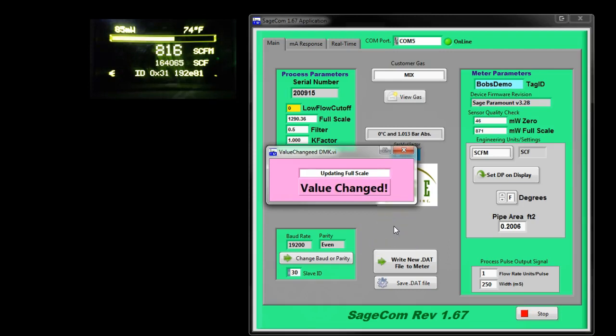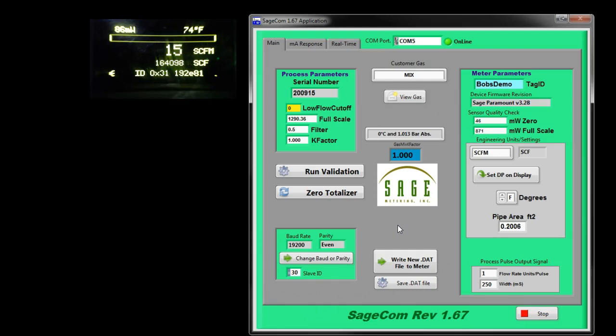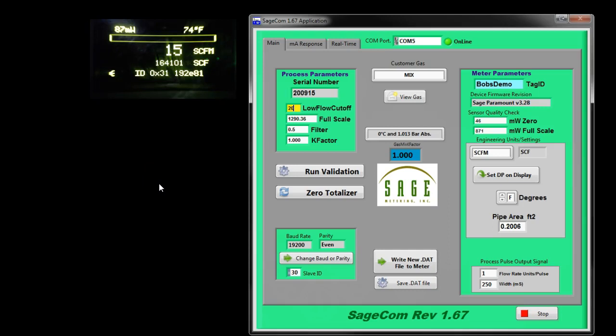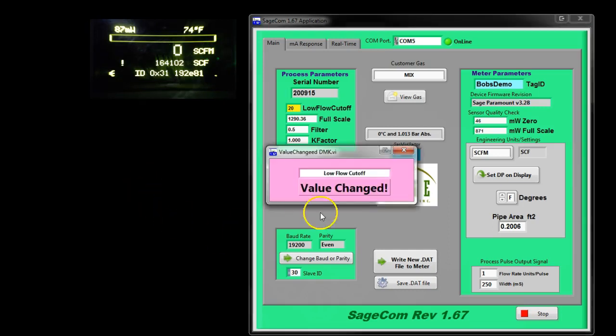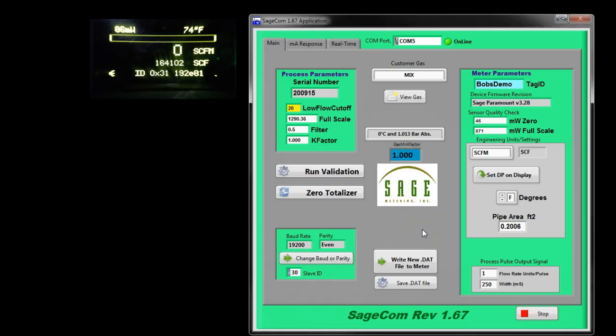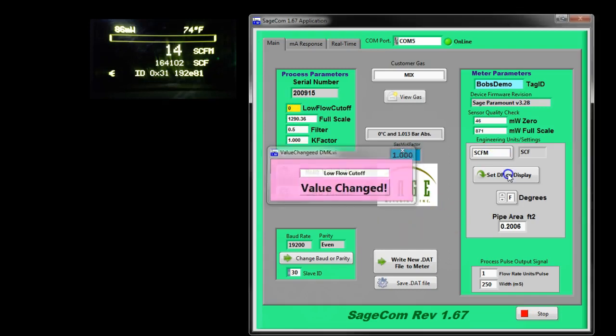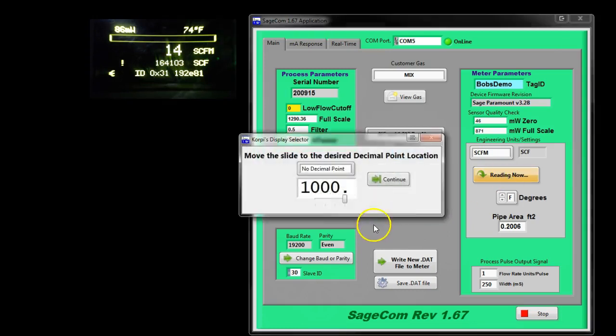You can actually change the low flow cutoff. Now what is a low flow cutoff? Suppose you're measuring the total and it's a critical application and it may be important that your totalizer is protected from reading when you're at no flow. And when you're at very, very low flows, our meter is so sensitive that you'll be able to pick up even turbulence in the pipe, especially in large pipes. So you may want to put in a low flow cutoff. So let's say I put in 20 on this application at 0 to 5,000. I'll press the return key. Changes. And guess what? The flow rate is now reading zero. Of course, I'm going to put it back to low flow cutoff and then we can continue reading. And the decimal point will even change that back as well.